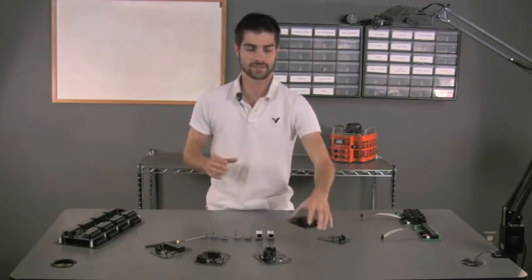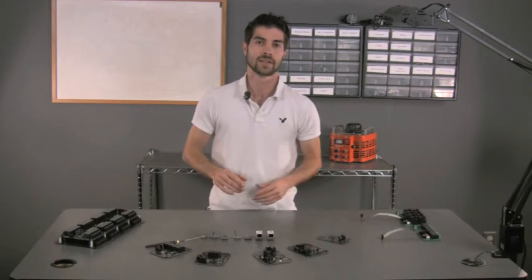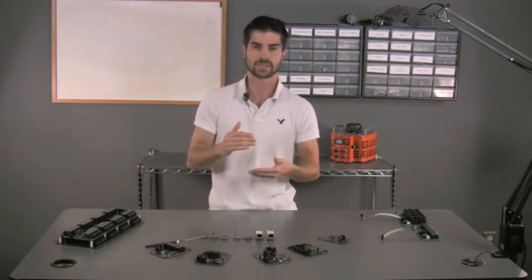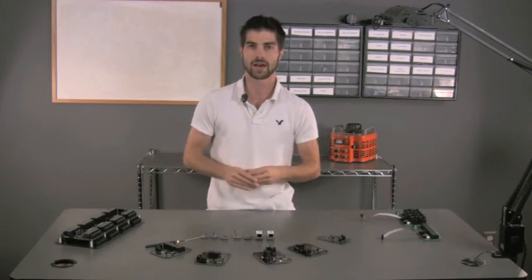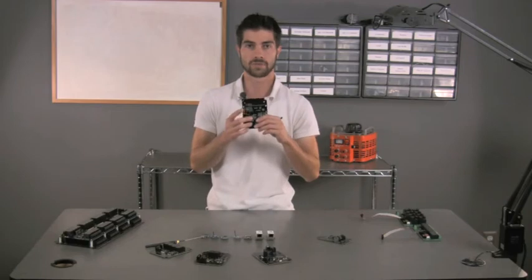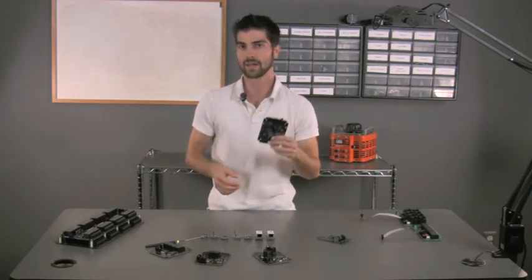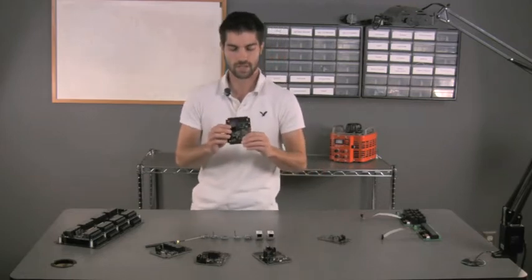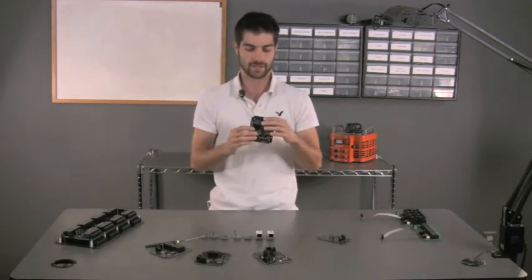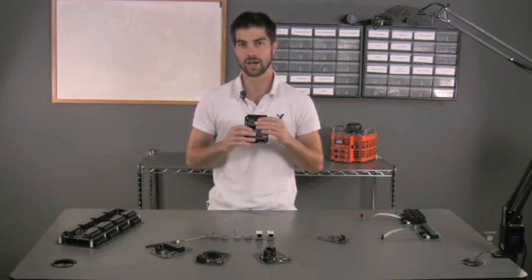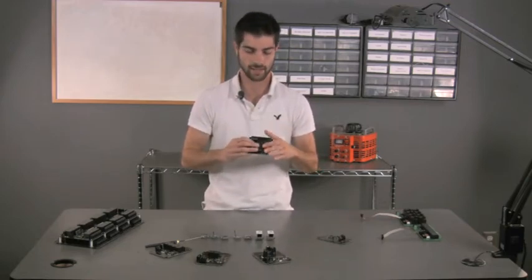Now, an event is what you configure. It's actually a time of day and then a specific command for the controller to carry out. That command could be something like just turn on one relay at 9 a.m. and then turn the relay back off at 9:01 a.m. Those would be two events. The first event would turn the relay on at 9 a.m. The second event would turn the relay off at 9:01 a.m.